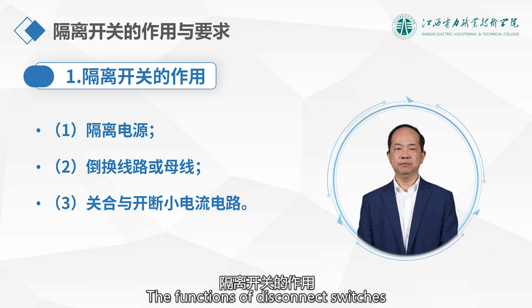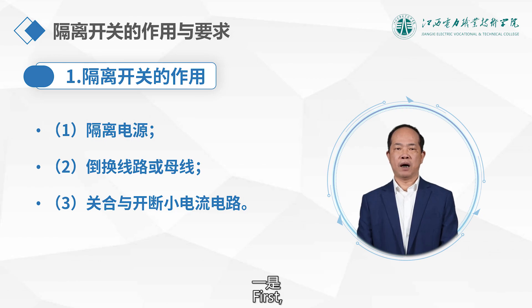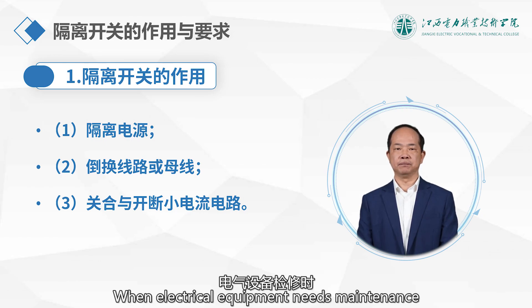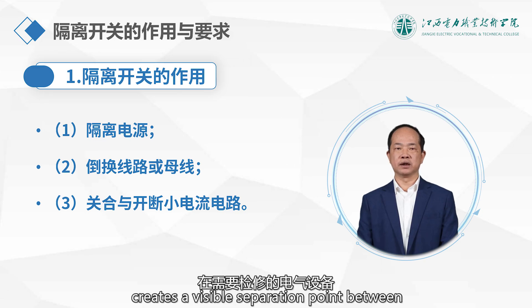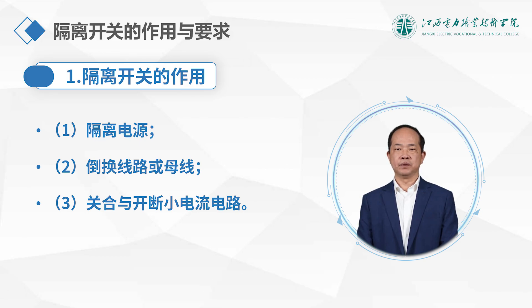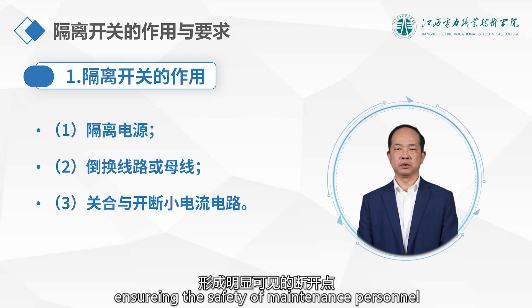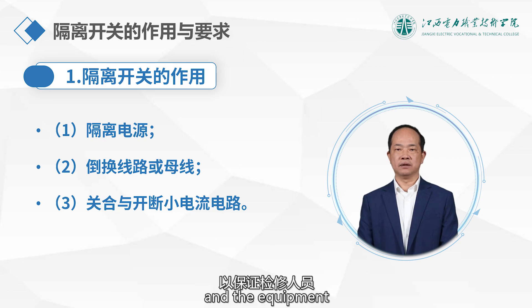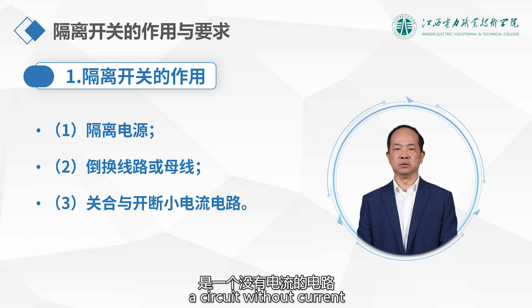The functions of disconnect switches can be summarized in three main aspects. First, to isolate the power supply. When electrical equipment needs maintenance, the disconnect switch creates a visible separation point between the equipment to be maintained and the live power source, ensuring the safety of maintenance personnel and equipment. It opens a circuit without current.